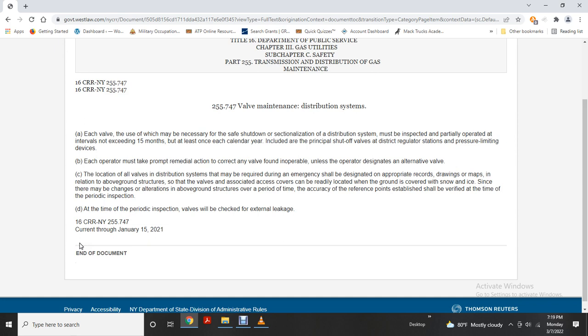To designate with the appropriate record, with the drawing or map, the relation of the above ground surface of the valve associated with the access of the covers will be readily located when the ground is covered with snow and ice. Since there may be changes or alterations of the ground structure over a period of time, the accuracy of the reference point established shall be verified at the time of the periodic inspection. At the time of the periodic inspection, valves shall be checked for external leakage.